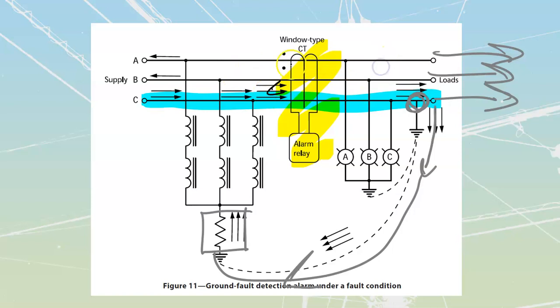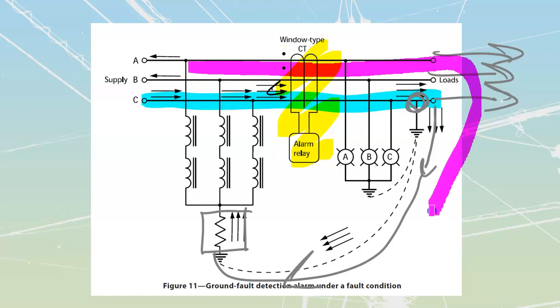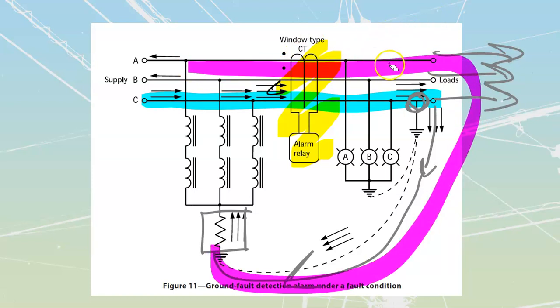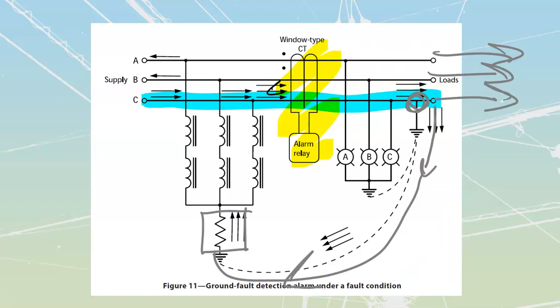But as soon as we get into this situation where some of our current is coming through but then circuiting around like that, this thing is now going to have a voltage potential across it, which means it is going to go into alarm. So the alarm relay is going to fire on at this point. My C line is going to go dark, and my A and my B line are going to get brighter, so I know which line it is that faulted.